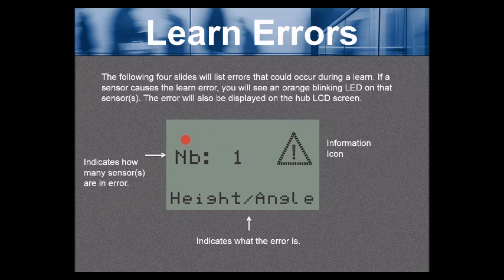Here, indicates how many sensors are in error. NB, number, abbreviation for number, and in this case we have one sensor in error. We also have an information icon, this triangle. Also, the error listed at the bottom of the screen, or bottom of the LCD screen, height angle, indicates what the error is. We'll address that shortly.